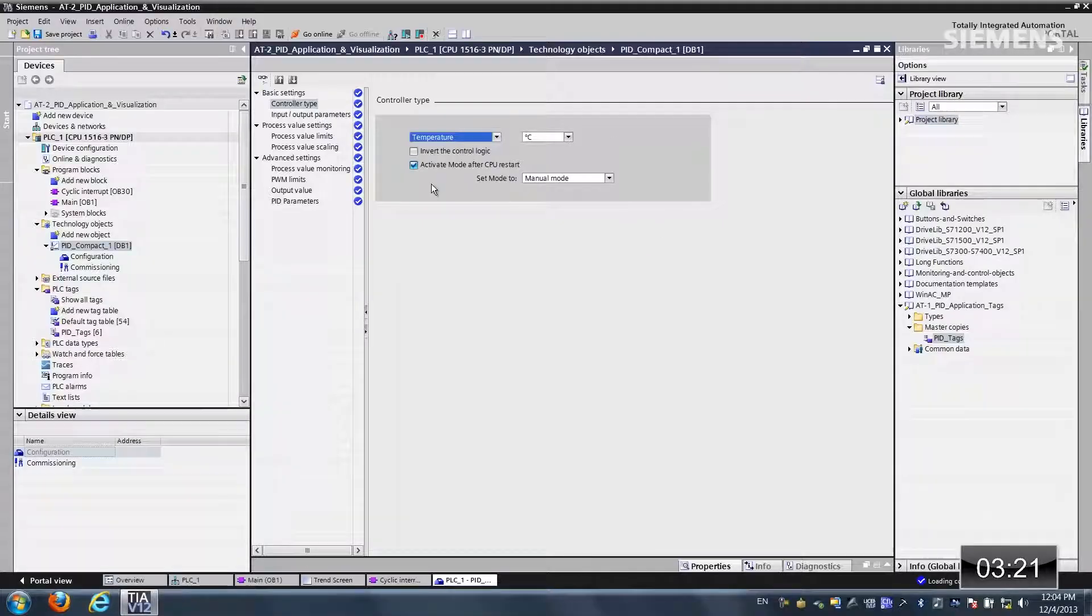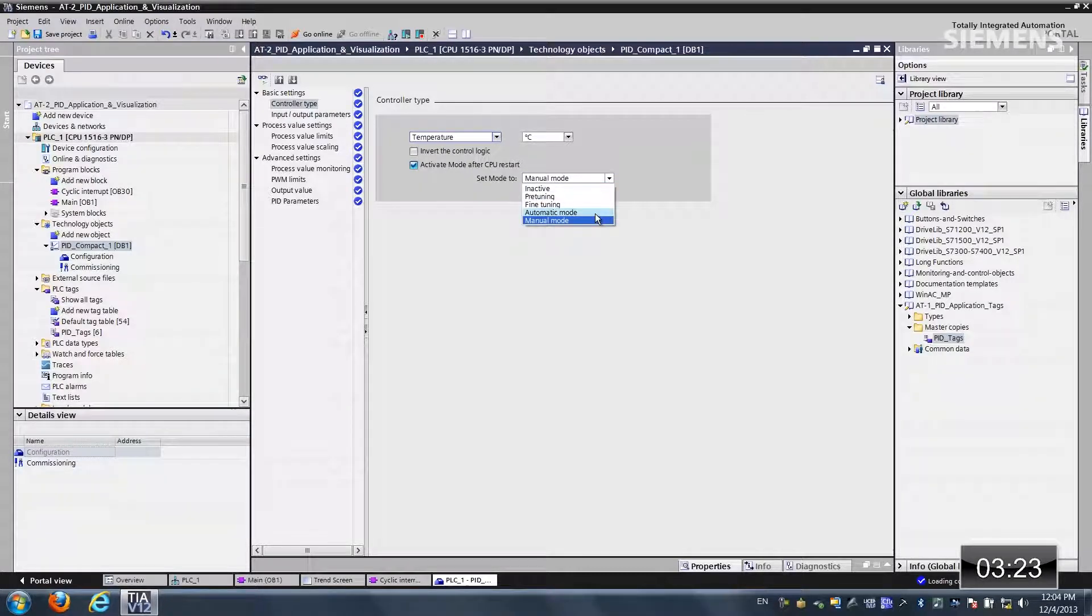And this is the version 2 PID compact. It has a couple of differences, one of which is right here, the set mode to. We can actually change it to automatic mode. That way if you go from start to stop or power cycle it, it always goes to automatic mode and starts up immediately.